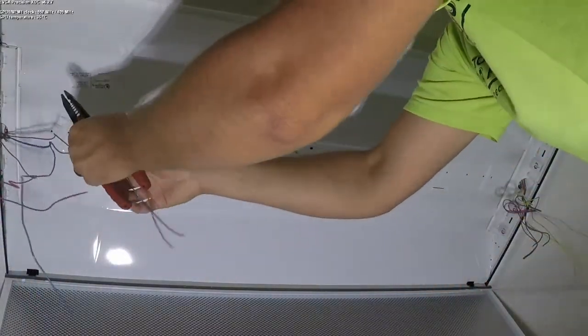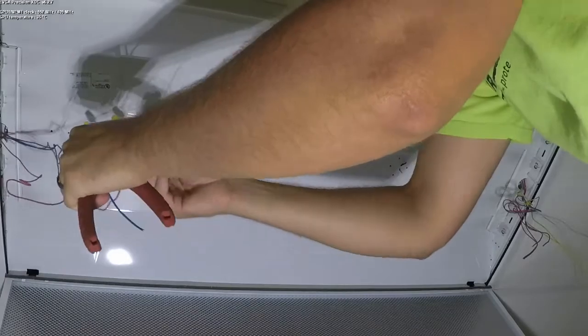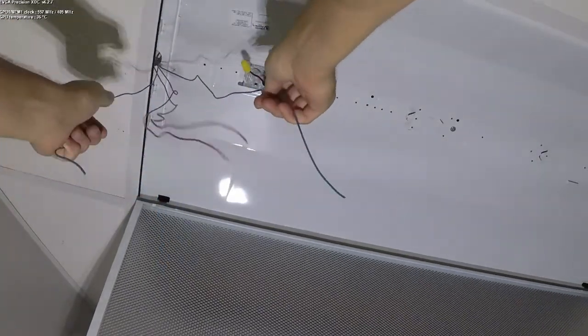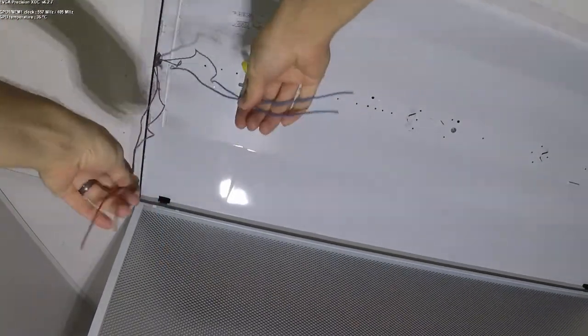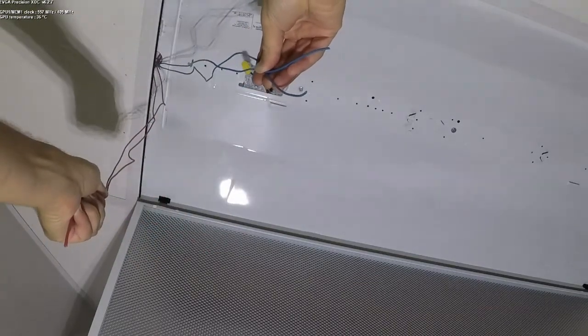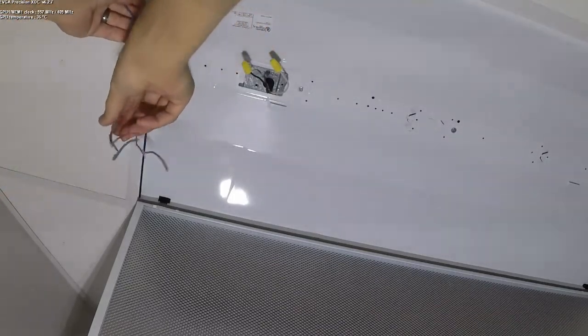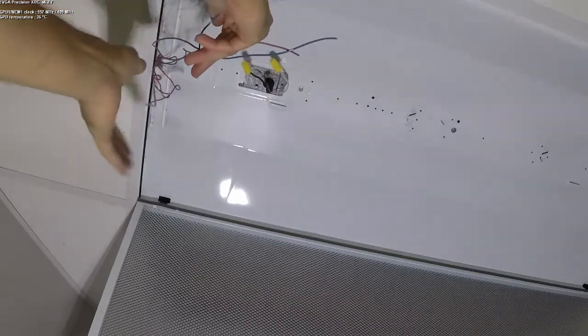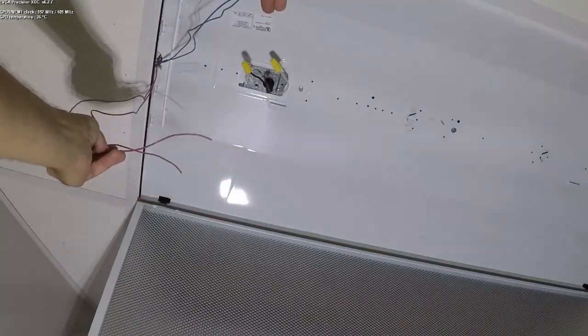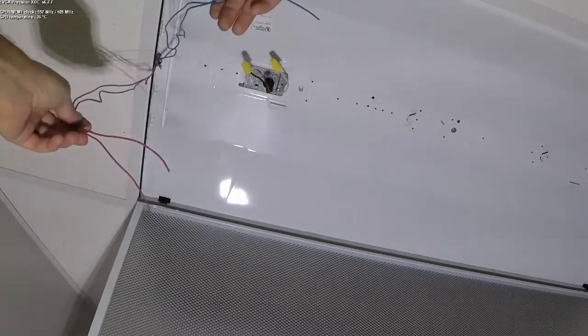Okay, so the way this is wired, each pair of wires goes to one fixture. After we cut out the yellow wires, we have two red wires and two blue wires. The two blue wires went to one bulb, the two red wires went to another bulb. So what we're going to have to do is take one blue wire to go to hot and take the other blue wire and go to neutral, and that will power up one bulb. And then we're going to take one red wire to hot and one red wire to neutral, and that'll power up a second bulb. So this will be either the two inner bulbs or the two outer bulbs.